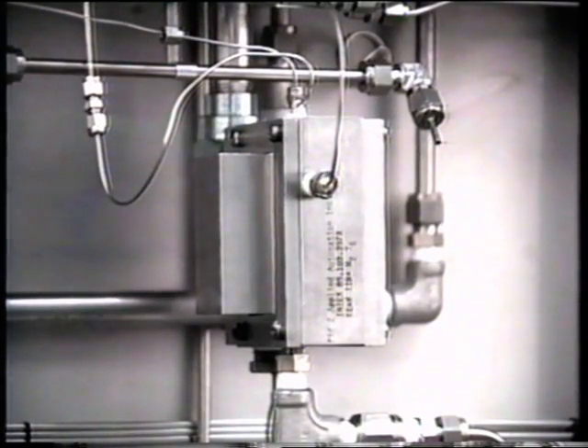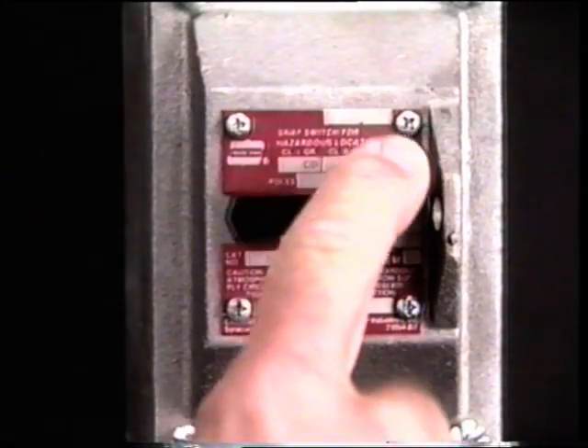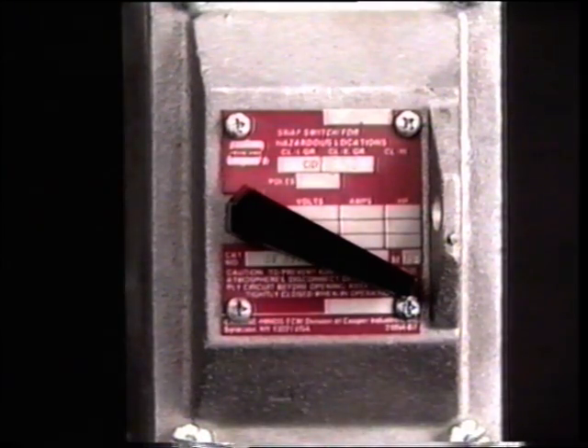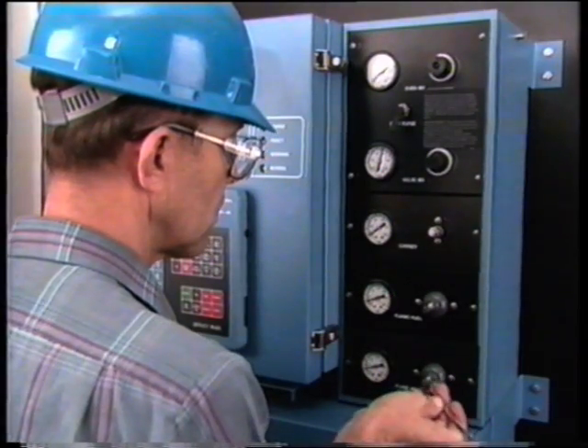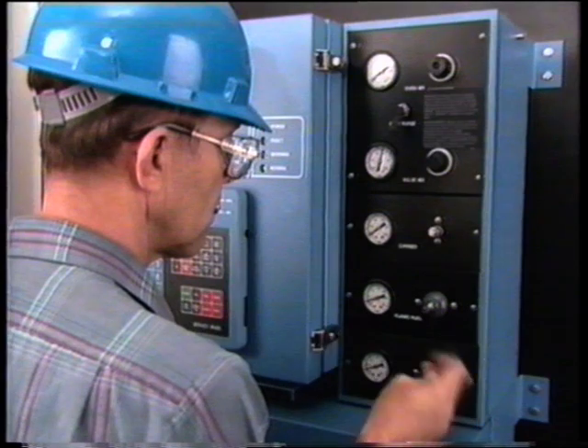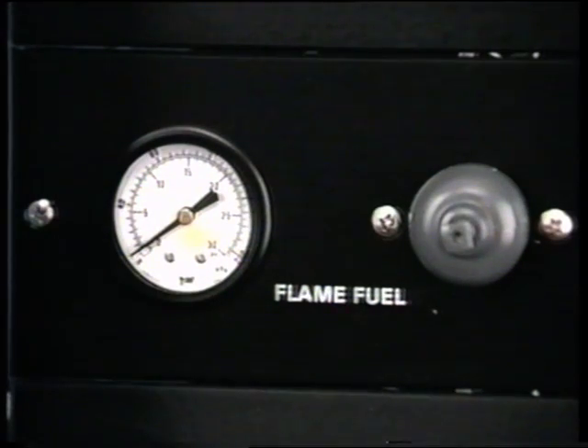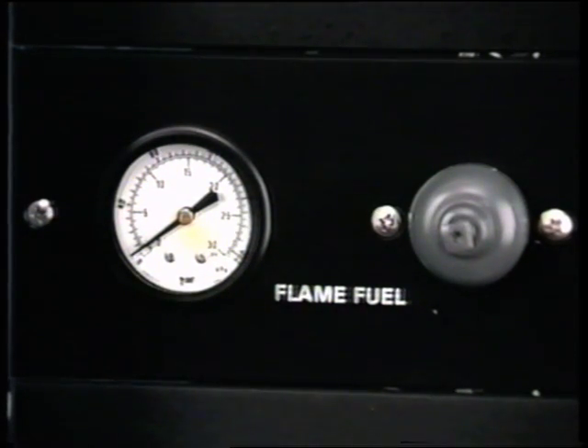Detector maintenance should include periodic cleaning according to the manufacturer's specifications. First, turn off the electrical power to the analyzer. Be sure that the carrier, flame fuel, and flame air are shut off. Do not begin cleaning procedures until all gauges indicate 0. Unless you suspect that the block needs replacing, there's no need to remove this detector from the oven when cleaning.